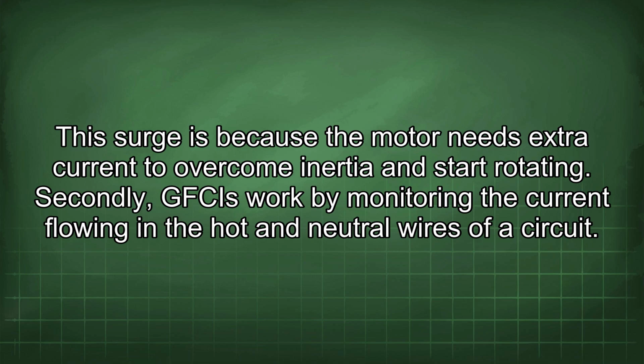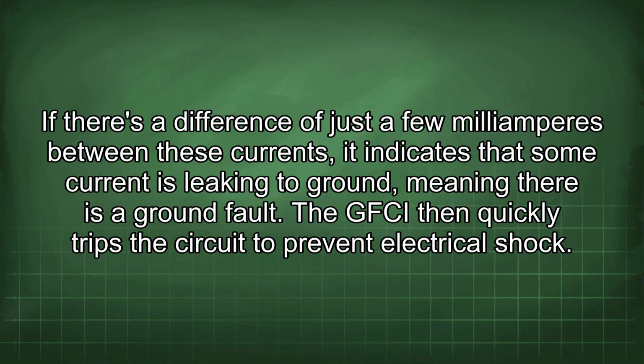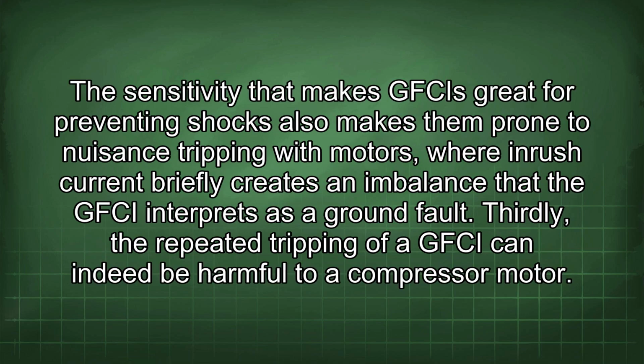Secondly, GFCIs work by monitoring the current flowing in the hot and neutral wires of a circuit. If there's a difference of just a few milliamperes between these currents, it indicates that some current is leaking to ground, meaning there's a ground fault. The GFCI then quickly trips the circuit to prevent electrical shock. The sensitivity that makes GFCIs great for preventing shocks also makes them prone to nuisance tripping with motors, where inrush current briefly creates an imbalance that the GFCI interprets as a ground fault.